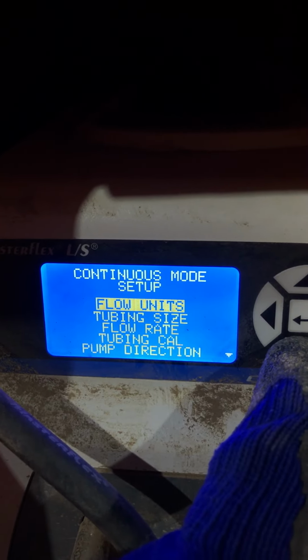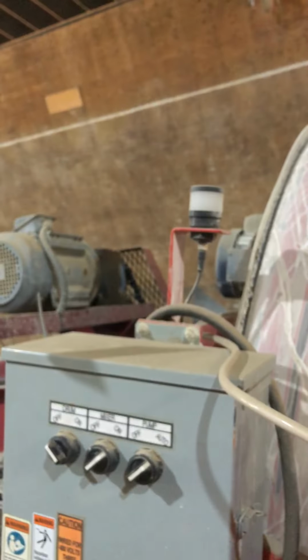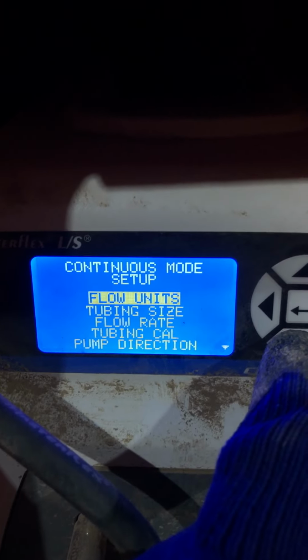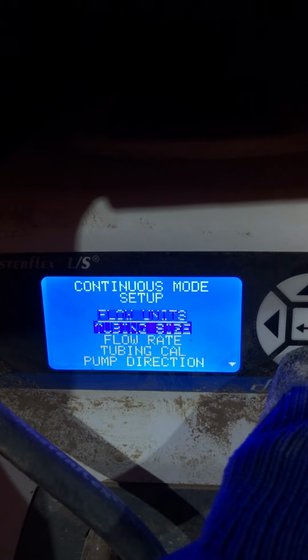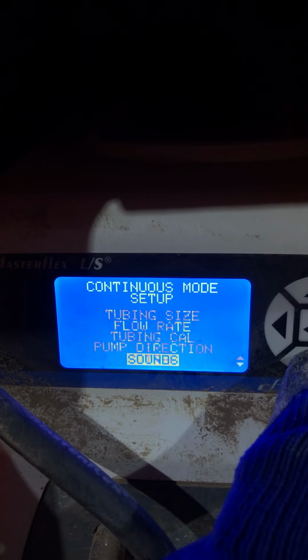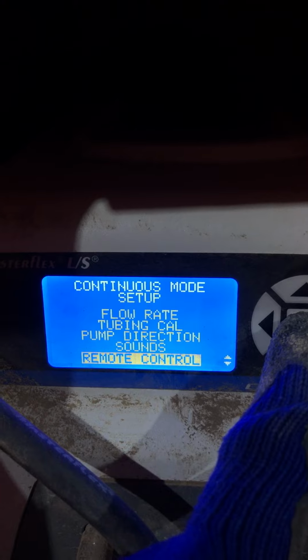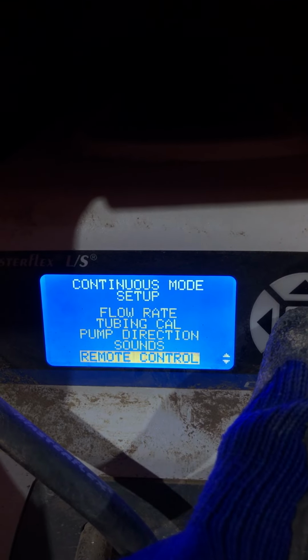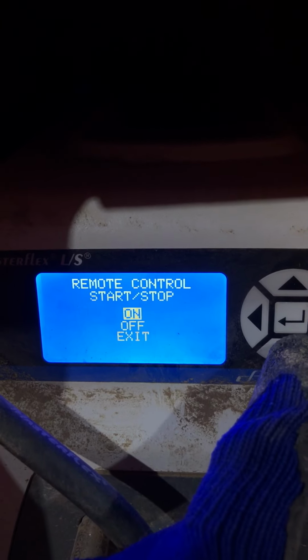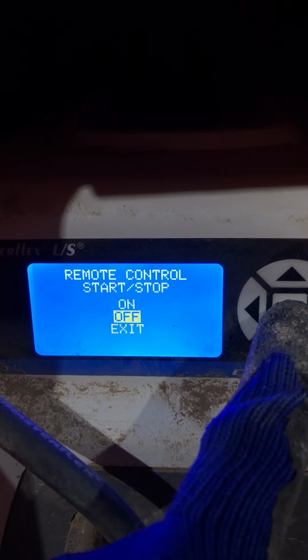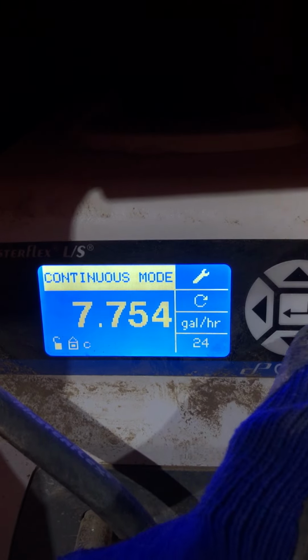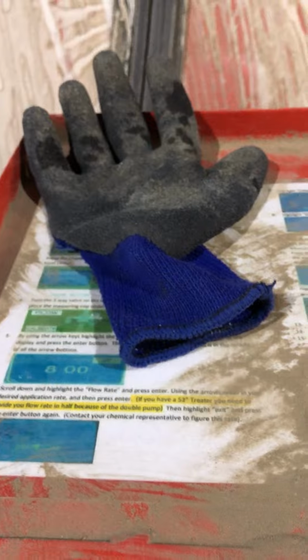It's important that the remote control, which is the switch that turns the drum, the switch in the drum I should say, be turned to off. Otherwise when you try to calibrate, that circuit won't be able to complete. So you go to remote control, local, remote control start stop, off. Okay, and we go back to the tools, and all these directions are on the inside of the cover with the exception of the remote control.